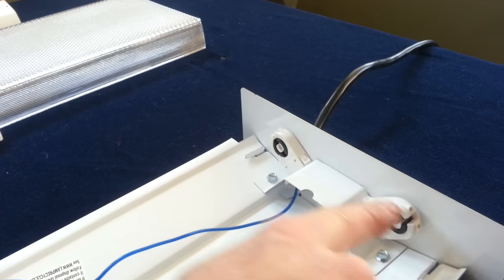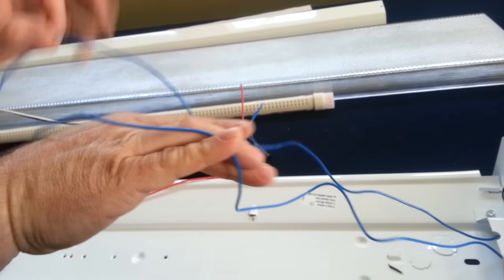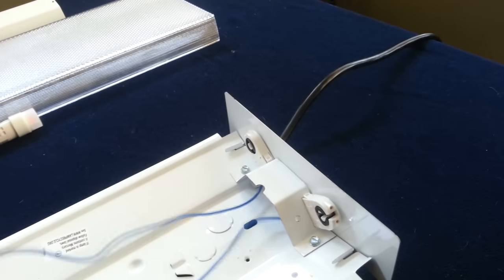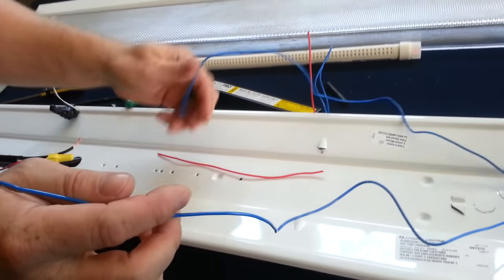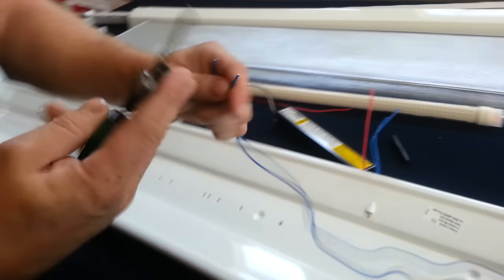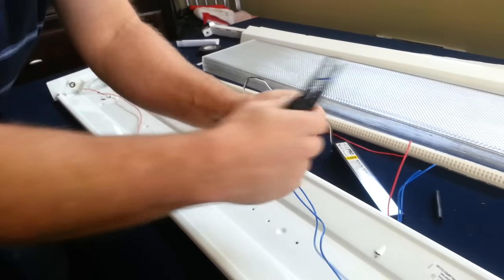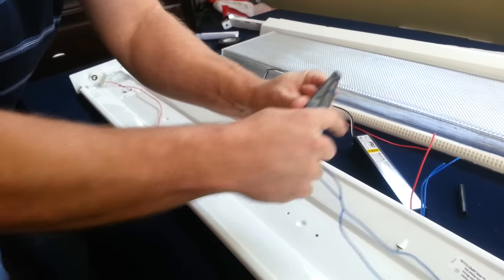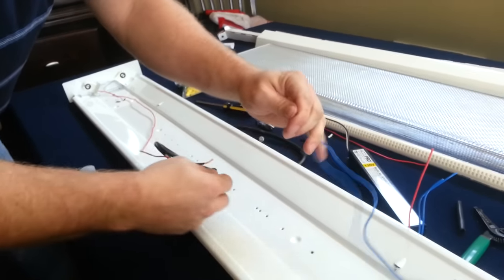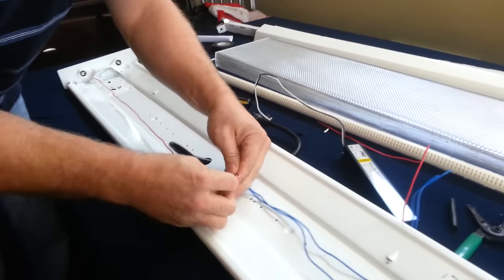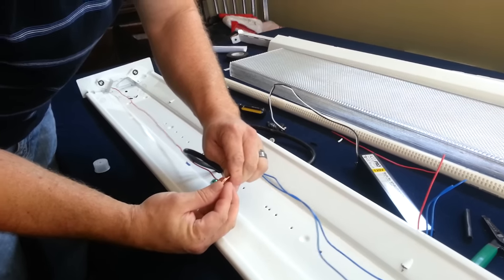If you look closely in here, you're going to see that this tombstone is not wired to this one. There's two wires coming off of each tombstone. So if there was a jumper where one wire went to the other one, we only need to use one of these. But since each one is wired separately, we'll use both of these. Strip them again down to about a half an inch.